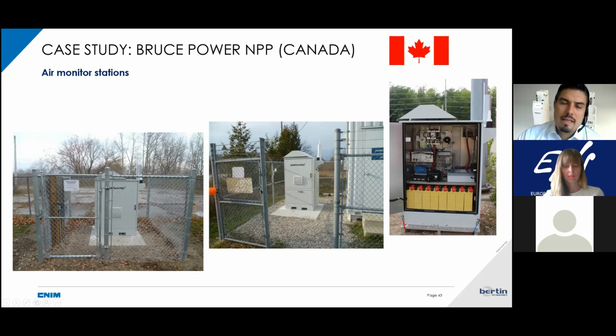As I said, a few of them are equipped with emergency power backup. It's tricky - you can imagine each aerosol air monitor needs to suck air through a filter, so you need a pump. Each pump needs some power, and to reach a low minimum detectable activity, to be sensitive, you need a bigger pump, because the flow rate is inversely proportional to your minimum detectable activity - double the flow rate gives you half the minimum detectable activity.